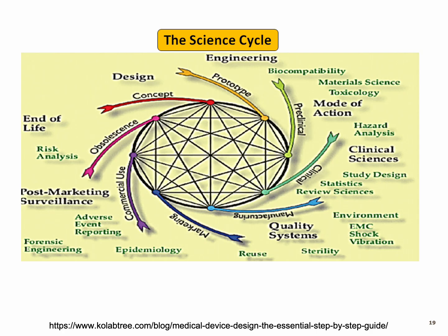Now, if you look into medical device production, you have two ways to look at that. You have a science cycle and you have a regulatory cycle. Here, I am talking about the science cycle. So everything starts on the top left with the design, where we can place the design here and you can look into the concept. So the concept is going to be based on the input, process, and output.